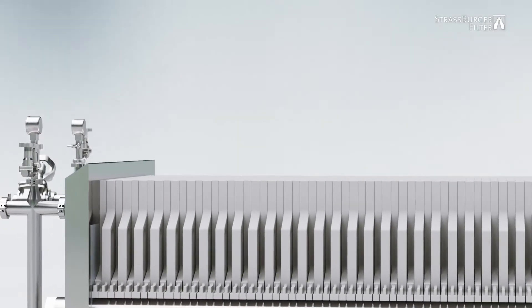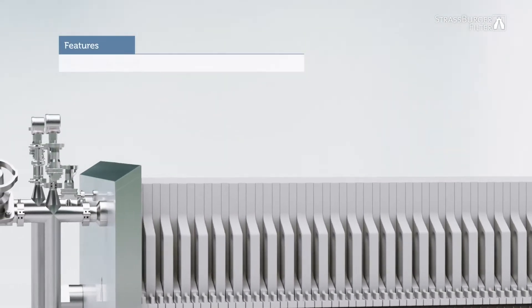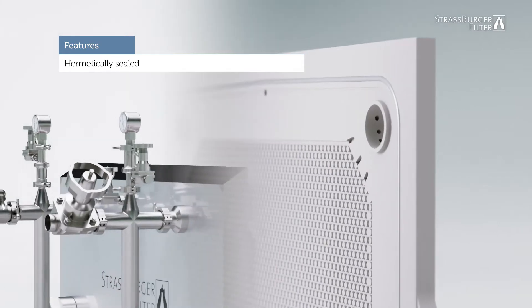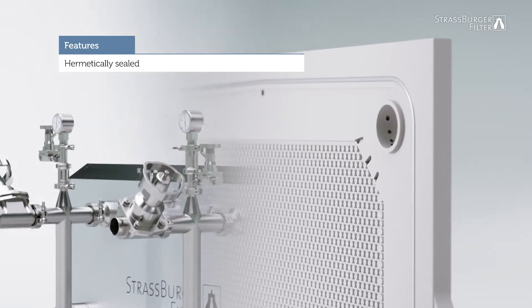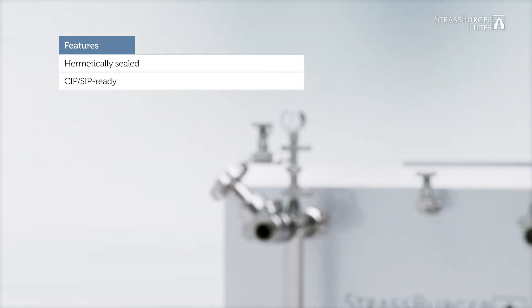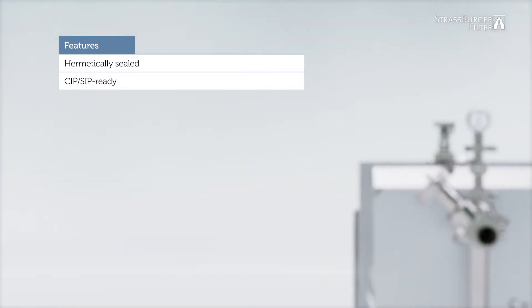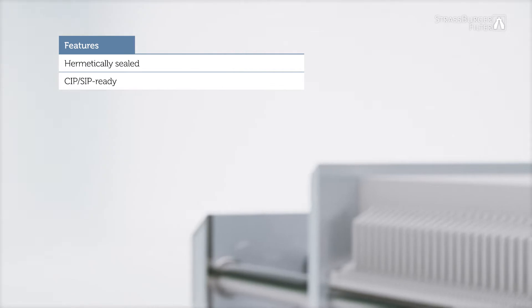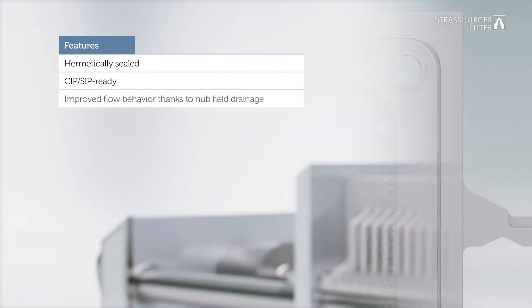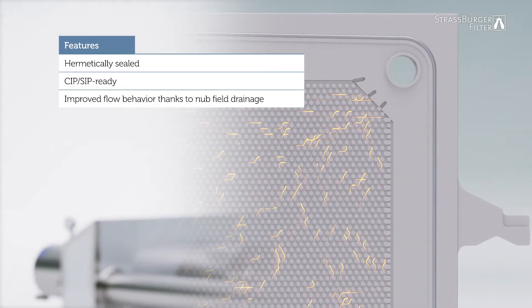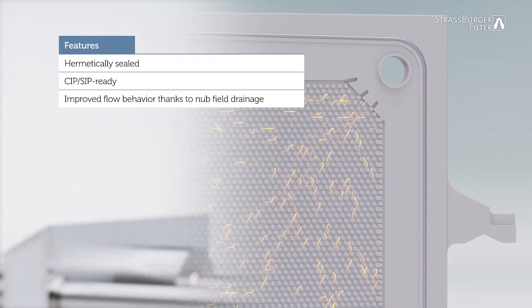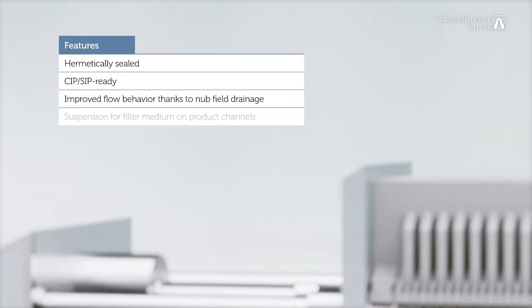The sheet filter has a few special features. The system is hermetically sealed by circumferential O-ring seals and can be cleaned by CIP cleaning and SIP sterilization with filter elements made of stainless steel. Compared to a ribbed field, the nubbed field drainage offers significantly improved flow behavior.